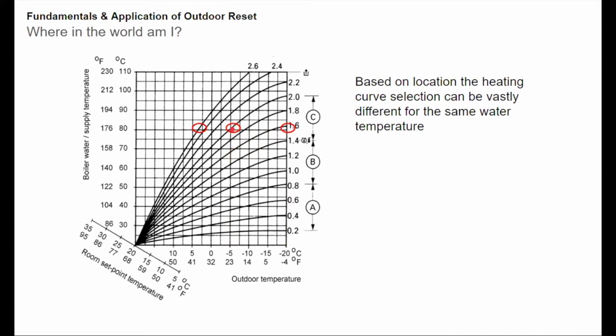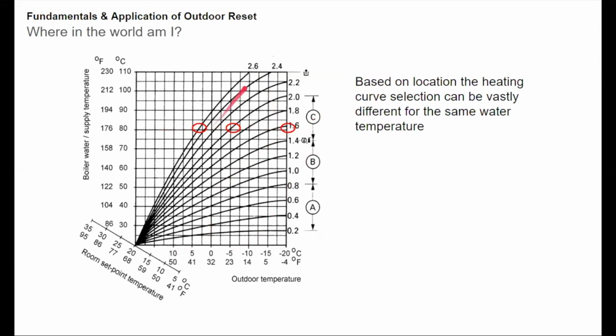That heating curve for a 23-degree outdoor temperature is more of a 2.0 curve. If I'm up around 43 degrees, think somewhere in maybe San Francisco, California, maybe somewhere a little bit south of there, and I need 180-degree water, that's about a 2.6 curve. So when we start to look at this, the thing to remember is the setup of it. I said it earlier, the heating curve is really based on outdoor temperature and water temperature. But for the same water temperature, depending on your location, which will also determine your design outdoor temperature, 180-degree water temperature could be anywhere from a 1.6 curve up to a 2.3 or potentially even higher. So it is something to remember when you start to look at setting these curves and where you are located. I say in the world, but we'll go North America because that's our main grouping of our presentations.